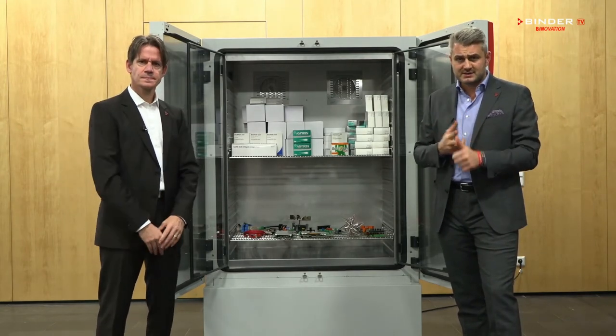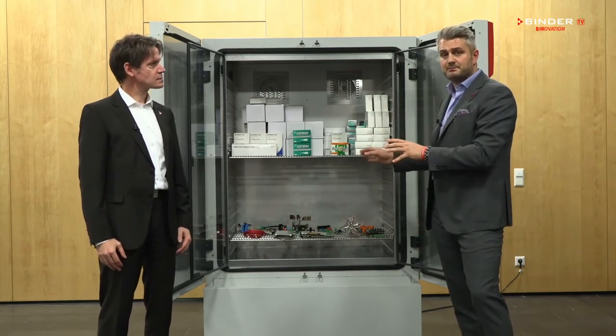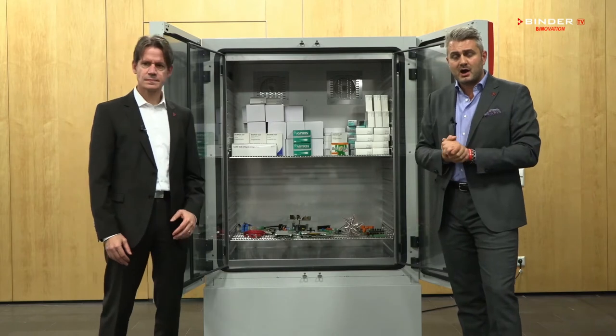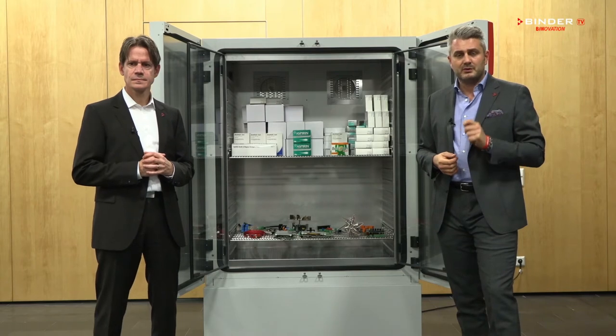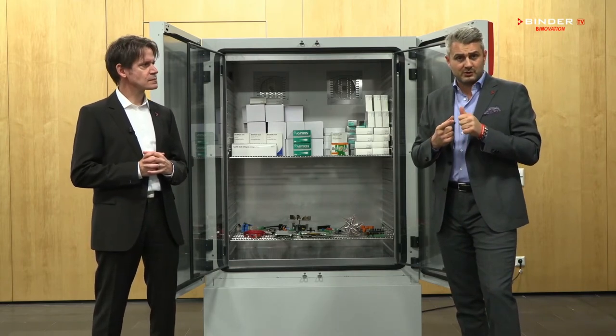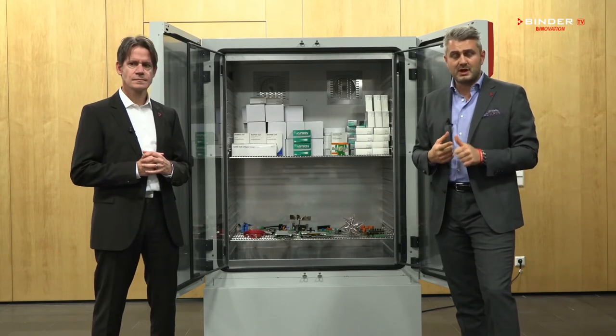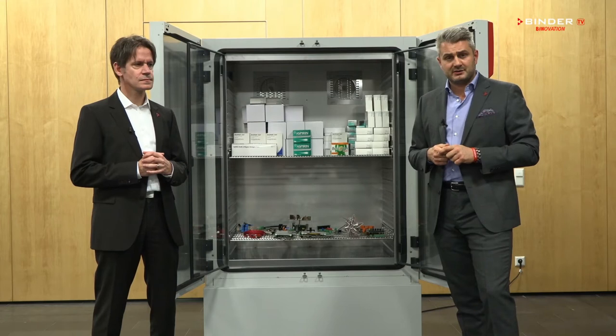Whether it's long-term, accelerated, or stress testing — all in one chamber. Also, our climatic chambers are always equipped with the APT-COM multi-management software, which allows the customer to remotely control the chamber and make any types of documentation required by the regulators.